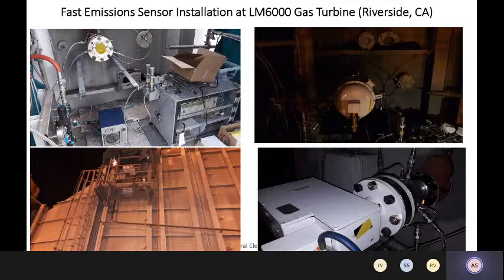So what are some of the features and applications of this fast sensing technology that we built up here? One of the features of this sensor is that it had improved concentration accuracy compared to some of the other traditional CEMS devices, because we are actually getting a line average of the gas concentration measurement, because light is actually going through the entire duct. The duct could be several meters wide, 5, 10, 15 meters wide, depending on the power plant. So you're getting a real average as light travels through the duct. With this, you can do better controls and probably better regulatory reporting as well.